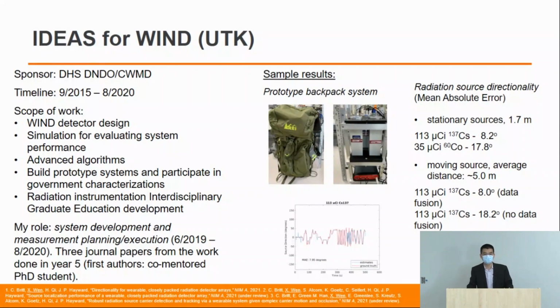And we tested this prototype system in terms of radiation source directionality. So if a 113 microcurie cesium source was stationary, and the distance between this source and the center of the detectors was about 1.7 meters, we could get a mean absolute error of about 8 degrees. And if we replace this source with a 35 microcurie source, the mean absolute error increased to about 18 degrees. This is because the signal to noise ratio from this source is smaller compared to the stronger cesium source.